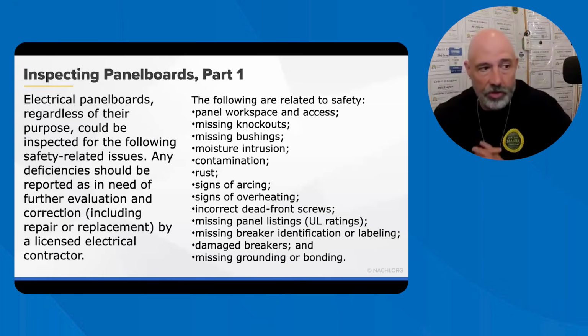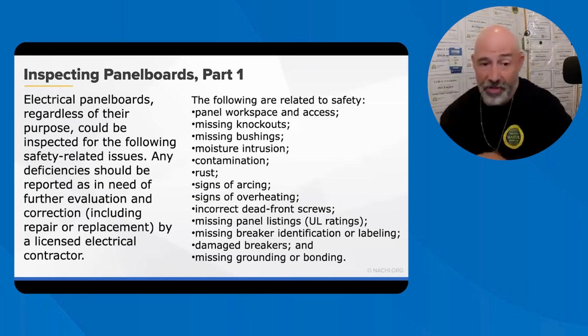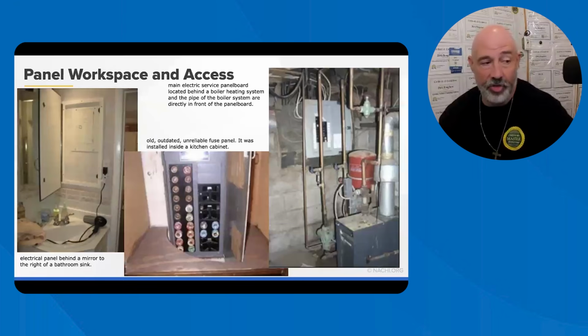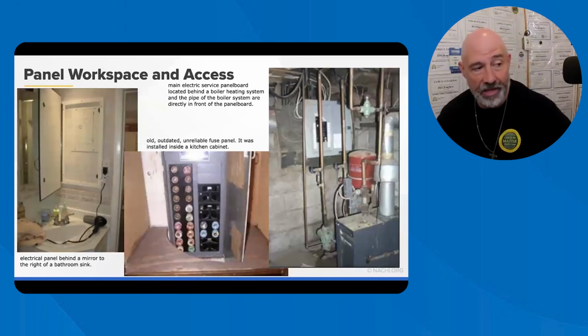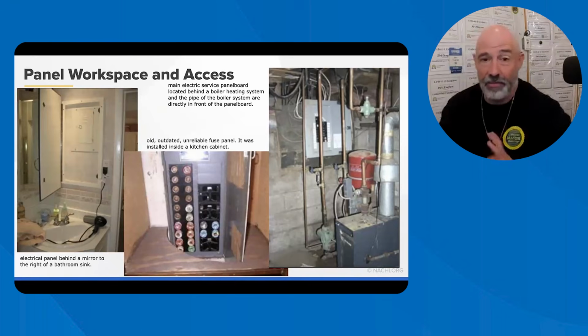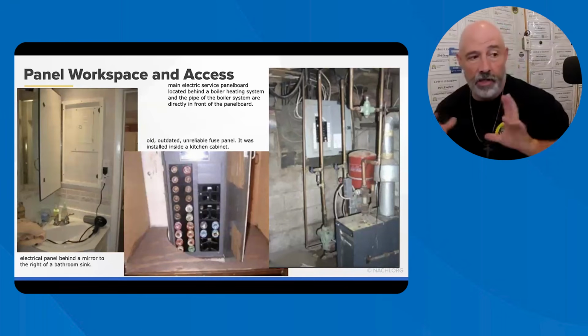Okay, inspecting panel boards. Take a screenshot of this. You want to make sure that everything's safe. We've talked about this: missing knockouts, the bushings, the water intrusion, anything that looks outside the normal, overheating, dead front screws missing, or if they're incorrect, if they're pointed screws or stuff like that. You want to make sure that you are doing a good job in calling this out. And a lot of times, if I see fuses in a house, I will call those out too and say, look, you might need to have further evaluation from an electrician.